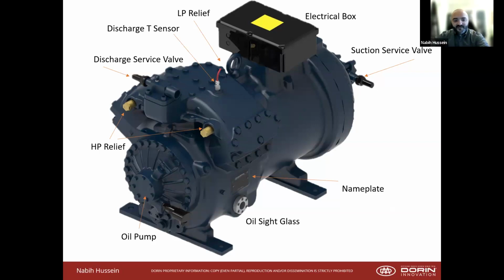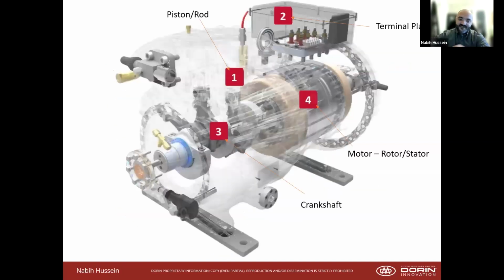The oil pump, depending on the size of the compressor, if it's a smaller size, you may not see that. It might use a splash disc on the inside. High pressure relief and then low pressure relief, you can't see it, but those will be on every compressor. A discharge temperature sensor, and right here's a discharge service valve. So you come up to a compressor in the field, you see one, this is what you're going to see, and these are the insides.